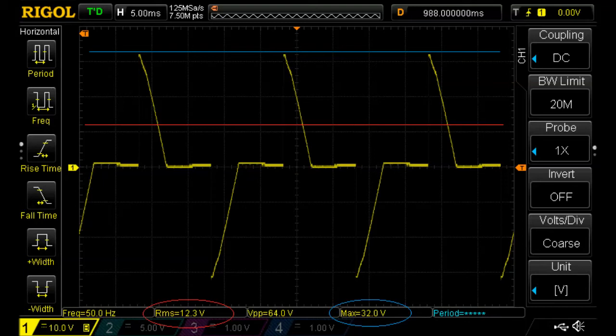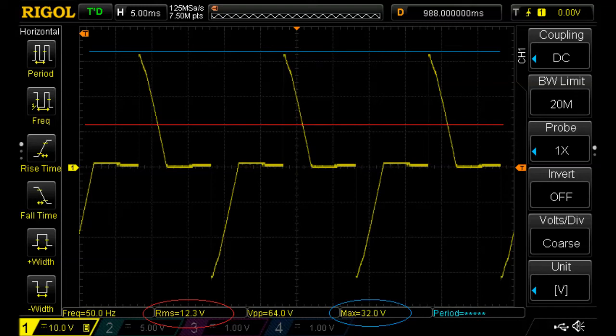And these 320 volts they are going through to the neon transformer will suddenly be giving out peaks of almost 17,000 volts instead of the 9,000 volts it should. So as I said over time the power amount will be the same but the voltage peaks will massively reduce the life of the tubes because they help in aging the electrodes much faster.